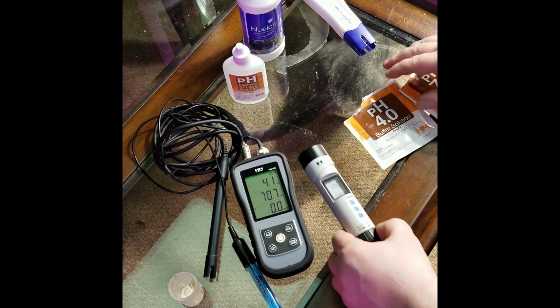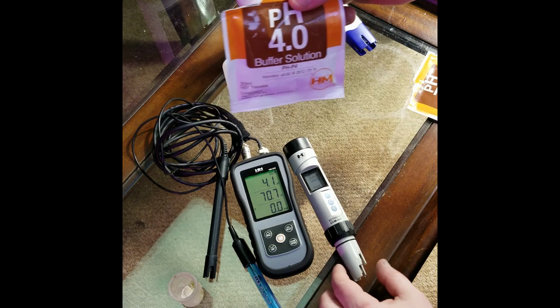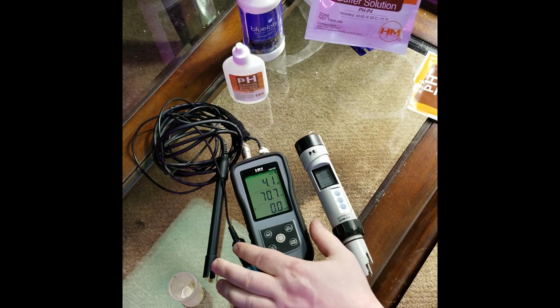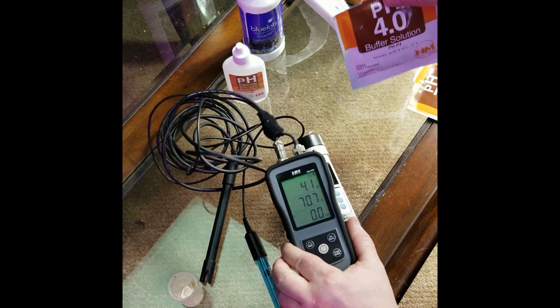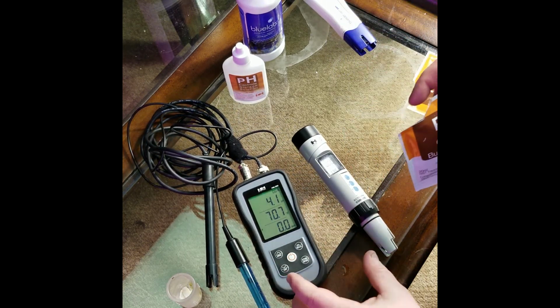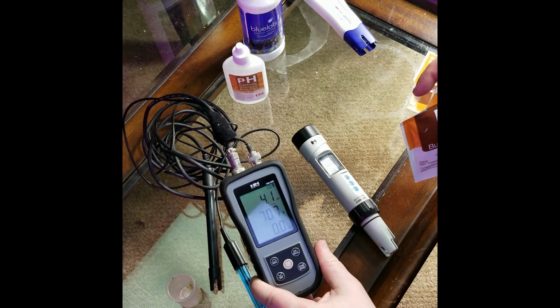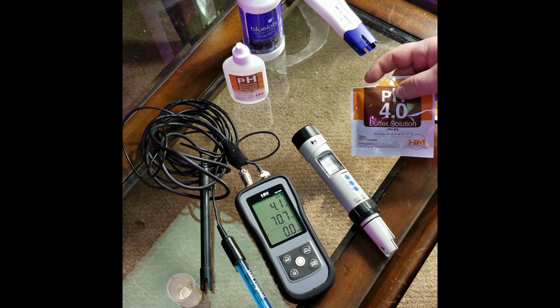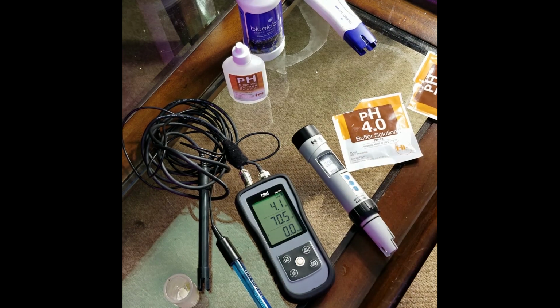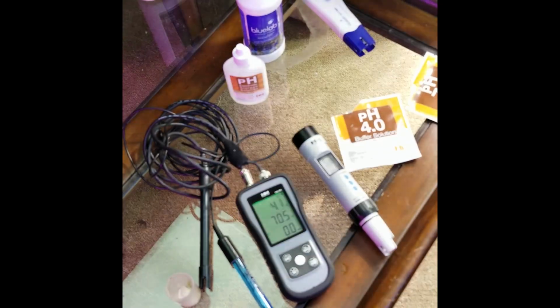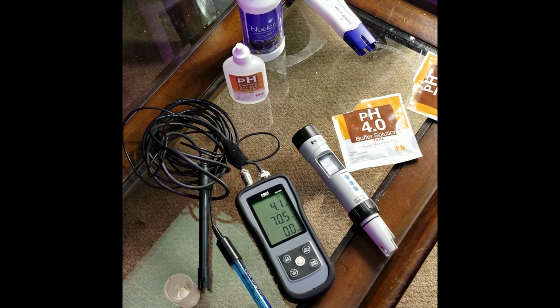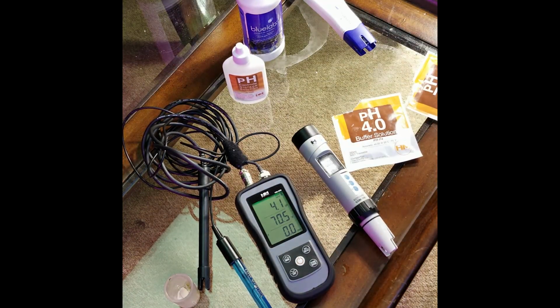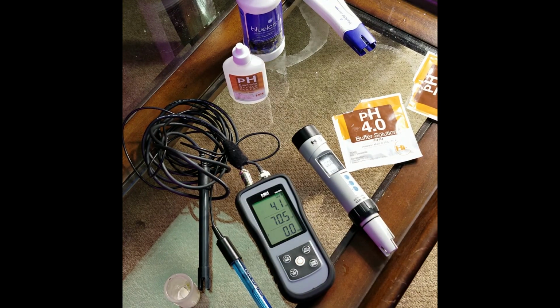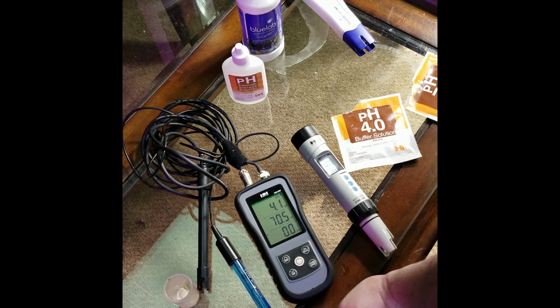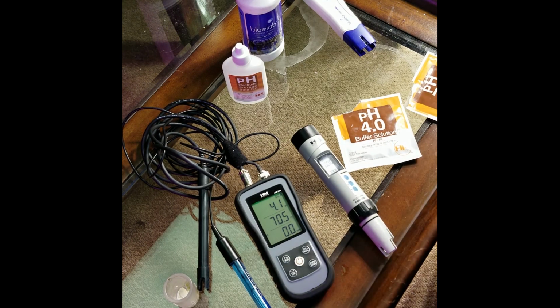So, the HM Digital meters, very fast responding. The bigger meters and the wall meters, which I have over there, are very similar to this. Wall mounted, battery powered and wall powered, and also backlight capable, which is very nice. But occasionally they do come into a situation where you want to clean it and calibrate it, because maybe while you're looking at it, you're not getting the correct readings, or it may seem like things are off.